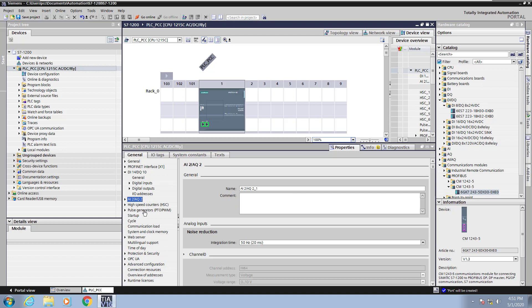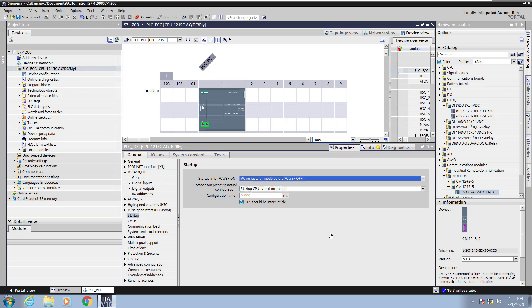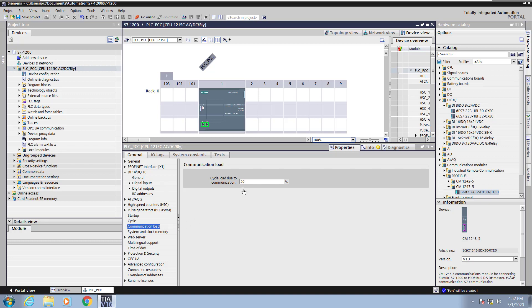You can configure your high speed counters, pulse generators, but I'm going to go over to the startup area. This is where you configure the startup operation of the CPU after POWER ON. What mode will the PLC start up in? Next I will select the cycle area. This is where you can set the maximum scan cycle for the PLC. So if this number would exceed the maximum number it would generate an error. The communication load is where you can allocate more time to handle communications or you can allocate more time to solve logic. So I'll increase that number to 40.